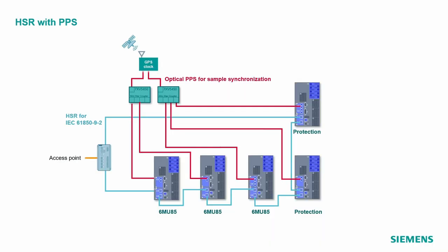So let's start with the first example, where we have one HSR ring and we use the PPS for the synchronization. So here it's clear that we need 2 different networks to distribute the 2 types of information. Through the blue line, we will see our sampled measured values being transmitted, and through the red line then we will see the pulse per second. For this we have external devices. We need a GPS and also the so-called star couplers to distribute the different signals to the devices. Keep in mind that all devices should be connected to the same level of the star couplers.